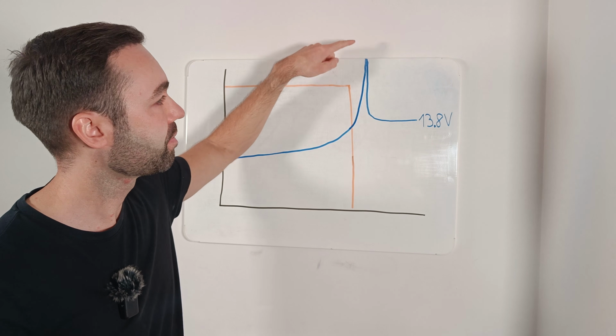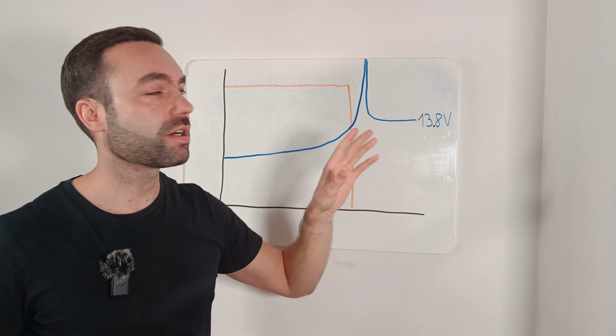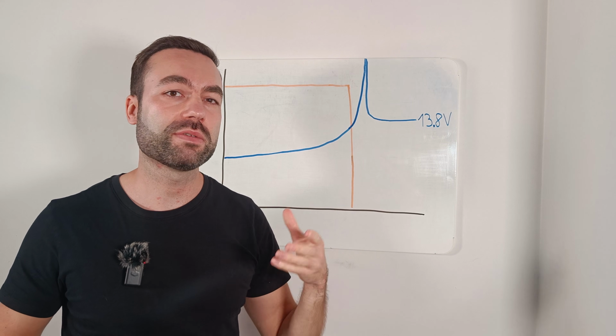Another lesser known problem is that a hard cutoff from high charging current to zero immediately will trigger a high voltage spike, which can cause the inverter to trip or even damage it. My recommendation is to look at how your battery behaves when it's nearly full — if the current drops from max amps to zero immediately, you have an imbalance issue.